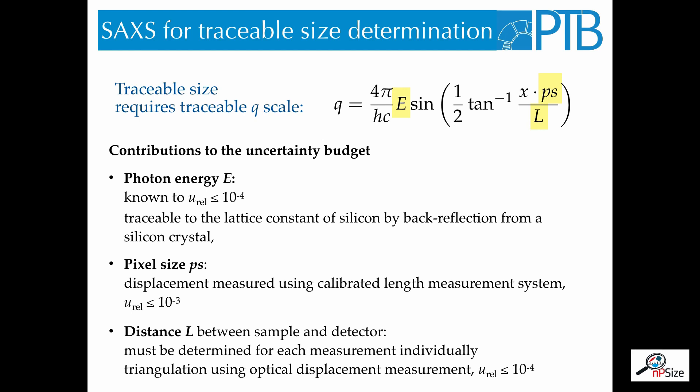The photon energy is known to a relative uncertainty of 10 to the minus 4. This has been measured by Bragg reflection of the synchrotron beam in a silicon single crystal, and therefore the photon energy is traceable to the lattice constant of silicon. The pixel size of the detector has also been previously measured by displacing the detector and measuring the shift of the scattering pattern on the detector. By this method, we get the pixel size of the detector with a relative uncertainty of 10 to the minus 3.